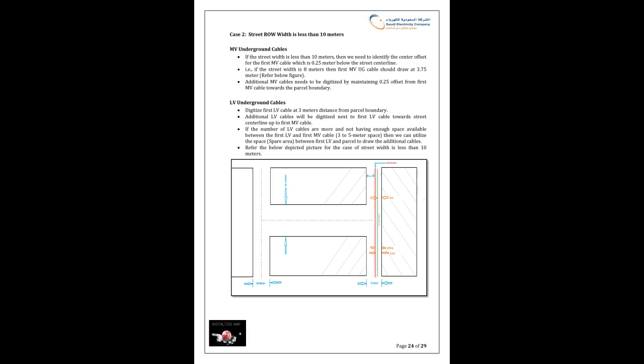LV underground cables. Digitize the first LV cable at 3 meters distance from the parcel boundary. Additional LV cables will be digitized next to the first LV cable towards the street centerline, up to the first MV cable. If the number of LV cables is large and there is not enough space available between the first LV and first MV cable, 3 to 5 meter space, then we can utilize the spare area between the first LV and the parcel to draw the additional cables. Refer to the picture below for the case of street width less than 10 meters.